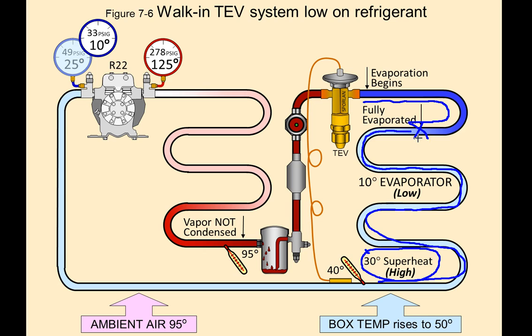The refrigerant boils off and changes state way too early, and then it just begins to pick up superheat, which doesn't give us any cooling whatsoever. So on the evaporator side we have low evaporator temperature because the lack of refrigerant lowers the pressures, and with that pressure-temperature relationship, when the pressure goes lower, so does the temperature. Then we have high superheat because there's not enough refrigerant in the system — the evaporator is starving, and that starving evaporator causes higher superheat.